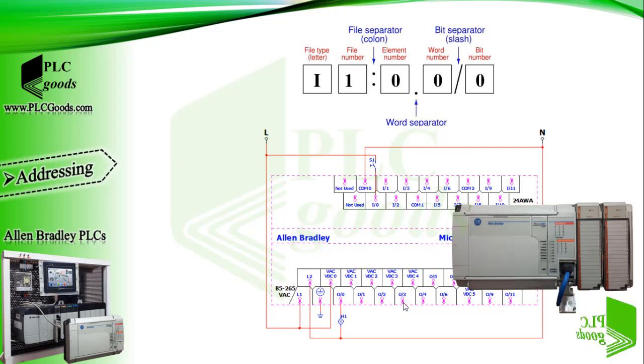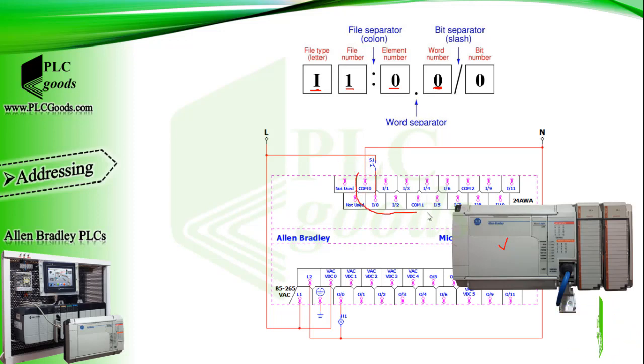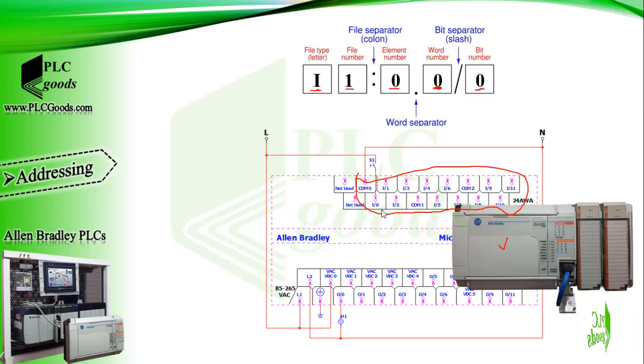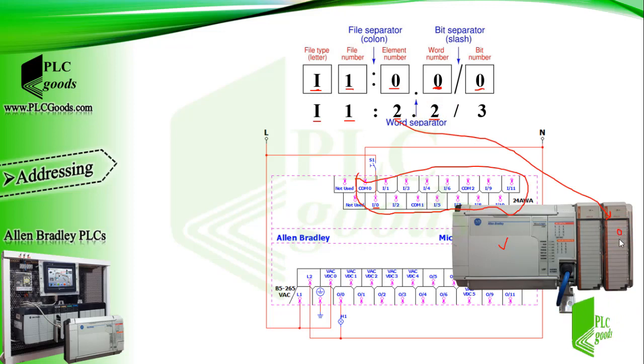Similarly, we can address PLC inputs. The letter I indicates the address is for a PLC input, and its file number is 1, which can be omitted. For my CPU the slot number is 0. My CPU has 12 digital inputs with word number 0, and I can refer to each digital input with a number from 0 to 11. For an analog input module in slot 2, this module supports 4 analog input channels, each using a word to store its input signal. Here I referred to the third channel, which has number 2.